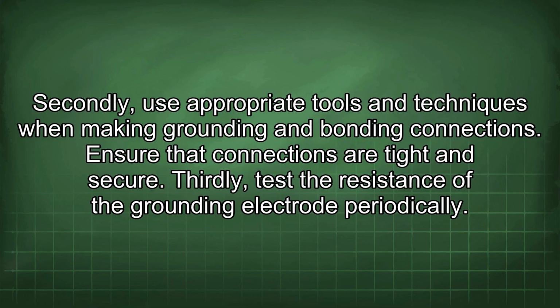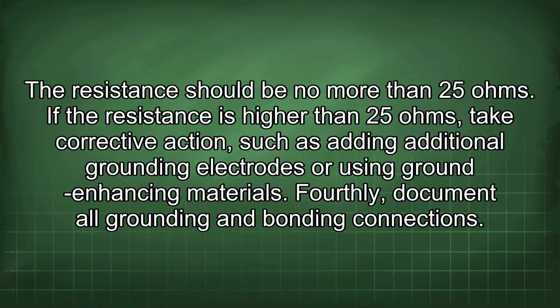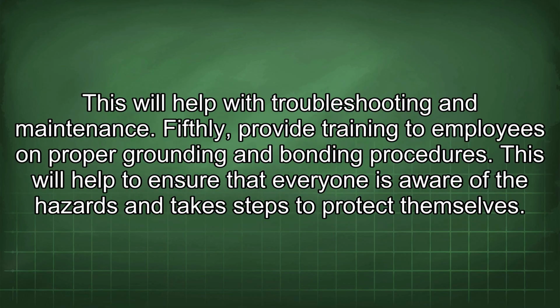Thirdly, test the resistance of the grounding electrode periodically. The resistance should be no more than 25 ohms. If the resistance is higher than 25 ohms, take corrective action, such as adding additional grounding electrodes or using ground-enhancing materials. Fourthly, document all grounding and bonding connections. This will help with troubleshooting and maintenance.